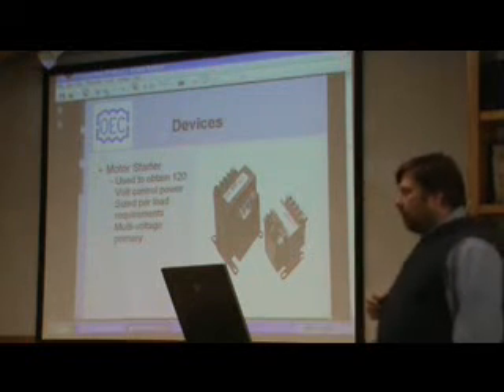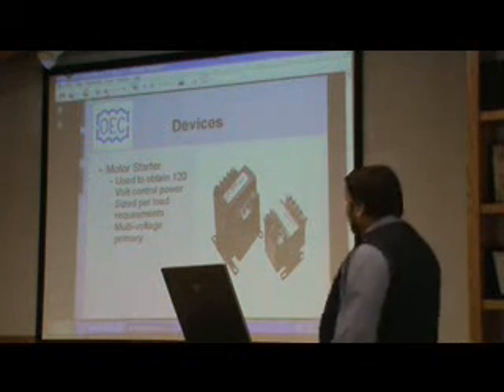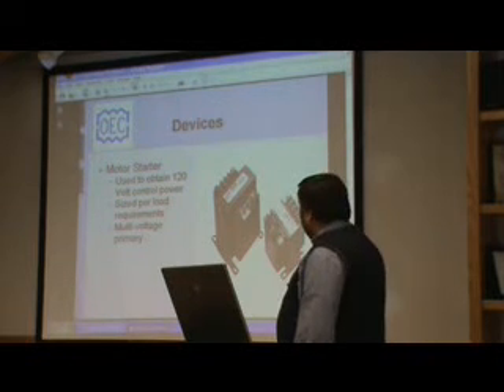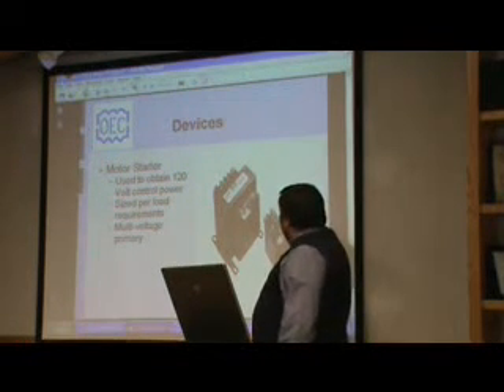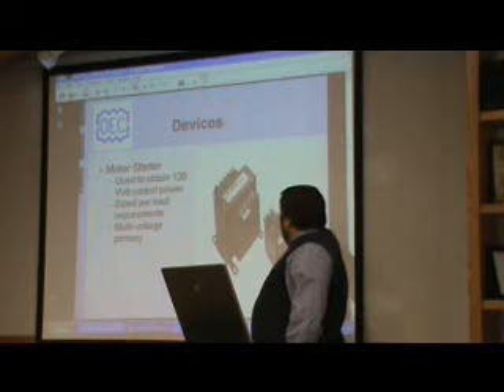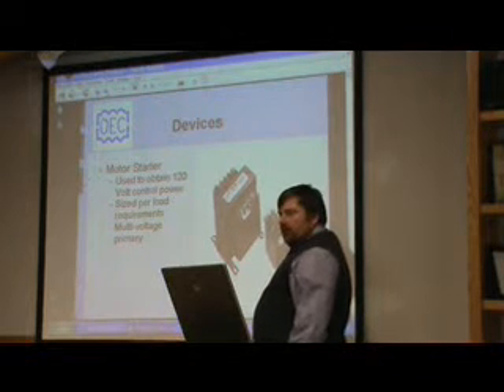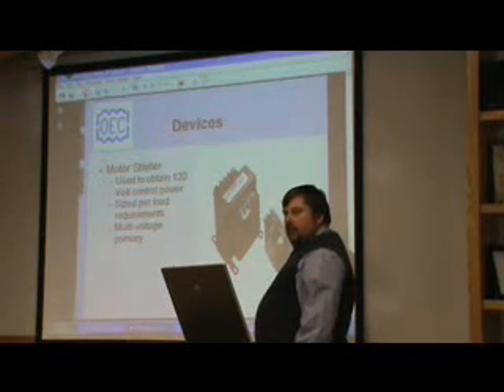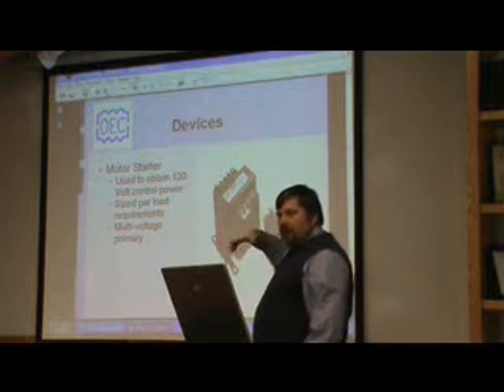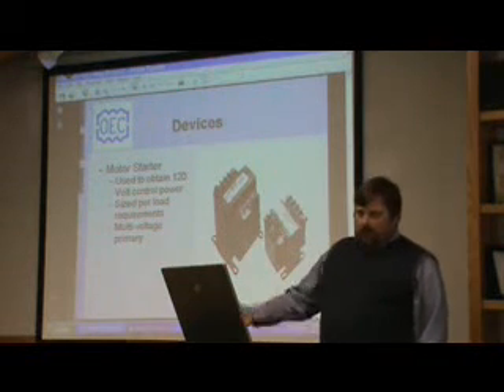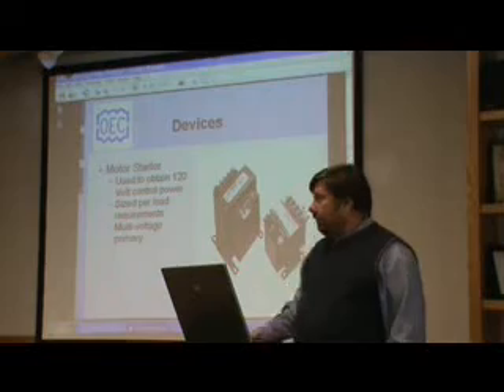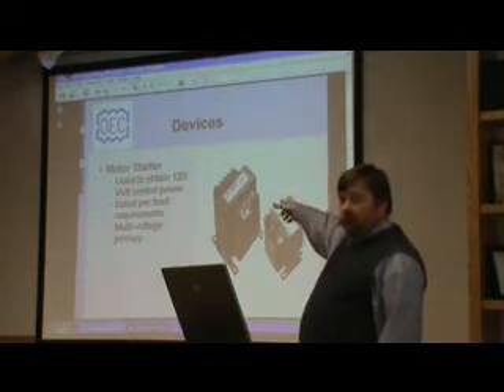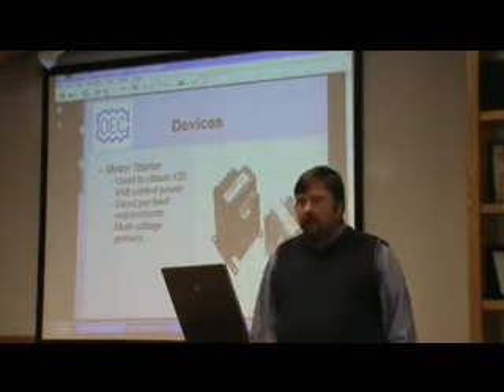All of the transformers that we supply in our panels have a multi-tap primary. What that means is on the primary side of the transformer, you can feed 208, 230, or 460. It's field settable. So if you buy a 480 volt panel and you get it out to the field and find you only have 230 volt power, it's as simple as moving the wire just one screw over, and now you've got your panel to work again.